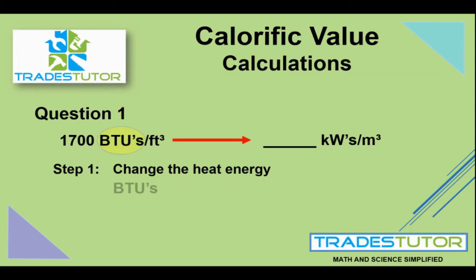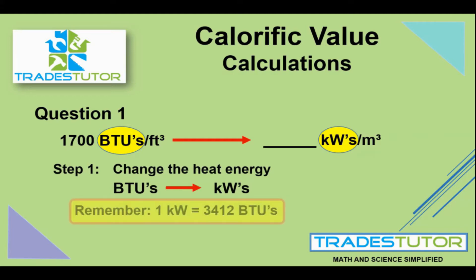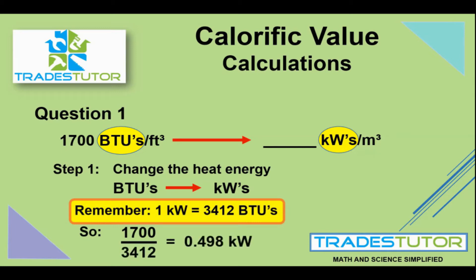We're going from BTUs to kilowatts — not changing the volume yet, just changing one version of heat into another. What we have to remember is that one kilowatt is 3,412 BTUs. So we take the number of BTUs we have and divide it by 3,412 to get 0.498 kilowatts.